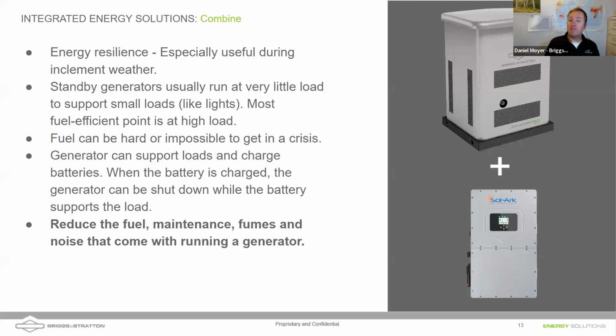One big thing is a lot of our generators have a histogram inside that tells you the load at which the generator has been run for its life. A lot of times we size bigger generators to start up motor loads, but when you're just running, a lot of generators are running at a quarter load or even less, just to keep the lights on in the home.